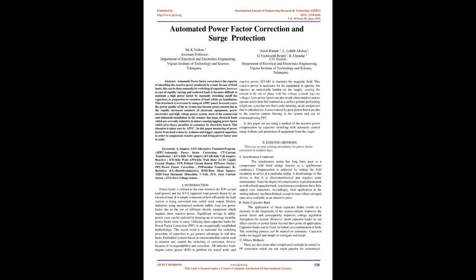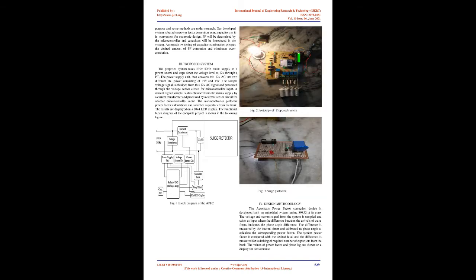Modern industries using mechanized methods suffer from low power factor due to the use of different electric equipment which requires more reactive power. Significant savings in utility power costs can be realized by keeping an average monthly power factor close to unity. Utilizing shunt capacitor banks for power factor correction, PFC, is an exceptionally established methodology. The recent trend is to automate the switching procedure of capacitors to get the greatest advantage on a real-time basis. Embedded systems based on microcontrollers can be used to monitor and control the switching of correction devices because of their dependability and execution. All inductive loads require active power, kW, to perform the actual work.